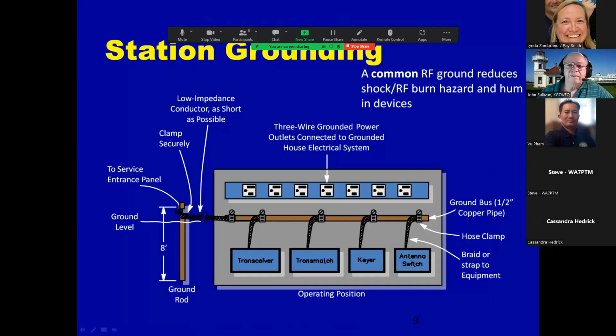For a proper RF ground, you have to use heavy gauge copper, not aluminum, preferably braid or foil, and keep the run as short as possible. Always remember you want short, straight leads, and avoid any bends as much as possible.